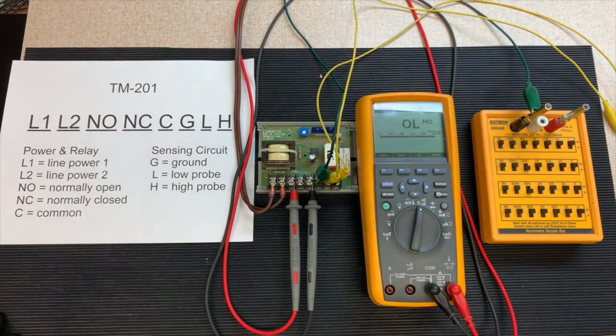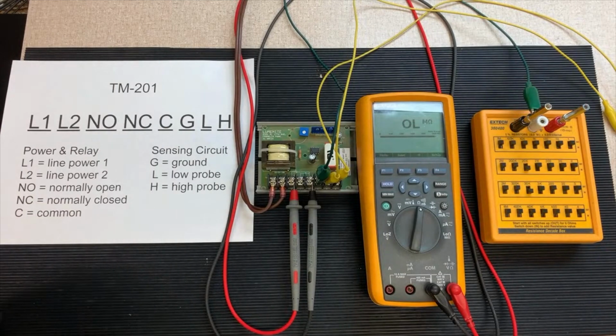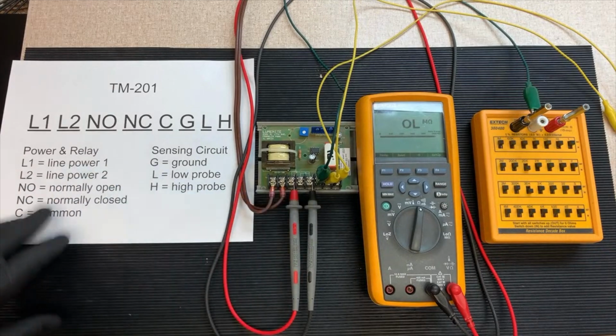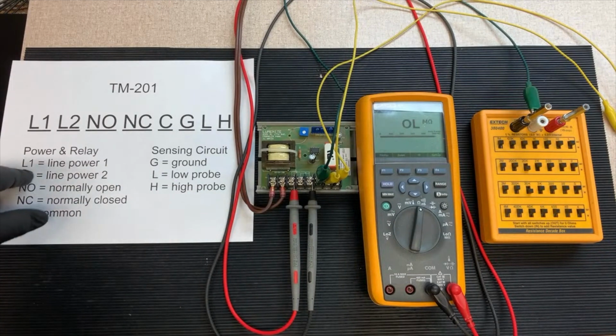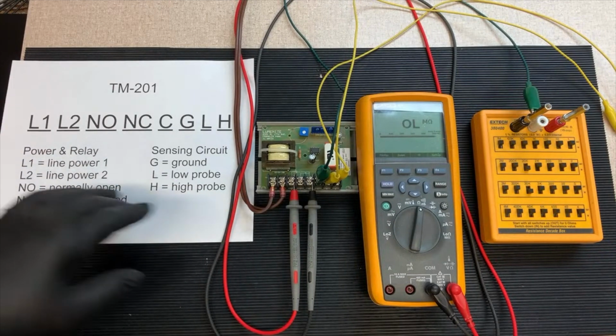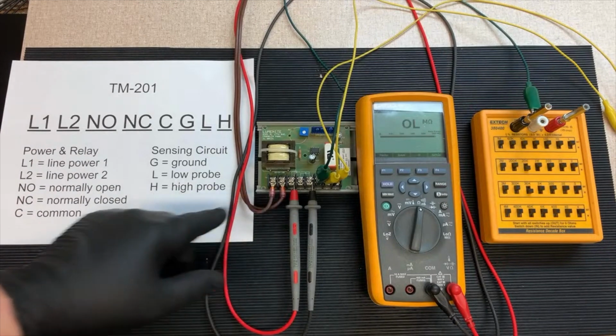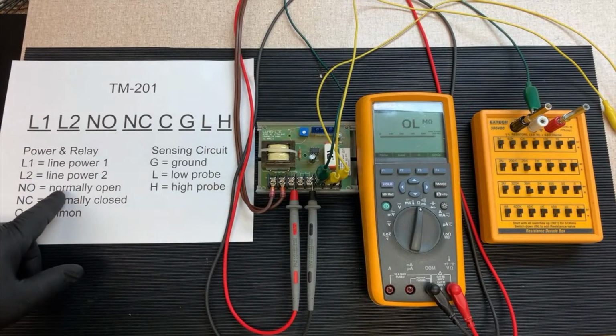So we're going to do a simple test here today with the TrackMount 201. All the terminals are labeled over here with a definition of what each one stands for. L1 and L2 are right here and here. That's your line power in, line 1 and 2. Your relay is next: normally open, normally closed, and common.